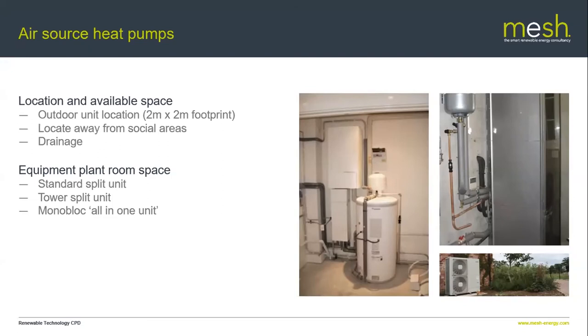Air source heat pumps come essentially in two flavors. You get what they call a split system, where there's refrigerant pipework that connects the outdoor unit with the indoor unit, and the indoor unit contains the heat exchanger between the heating water and the refrigeration side.